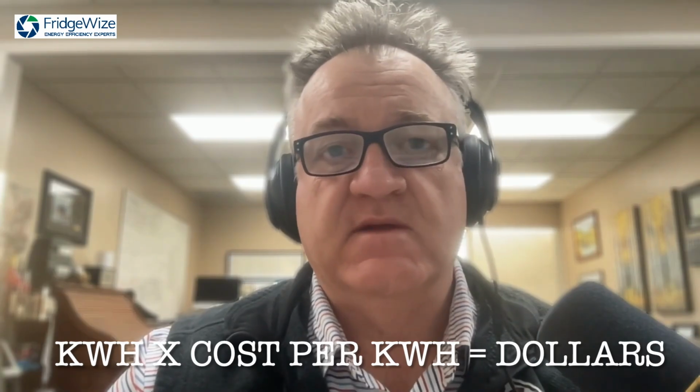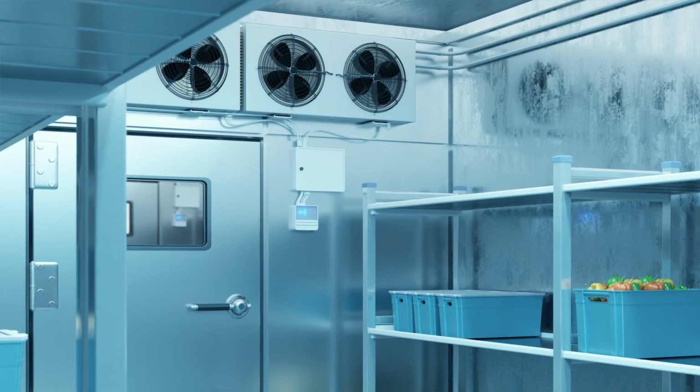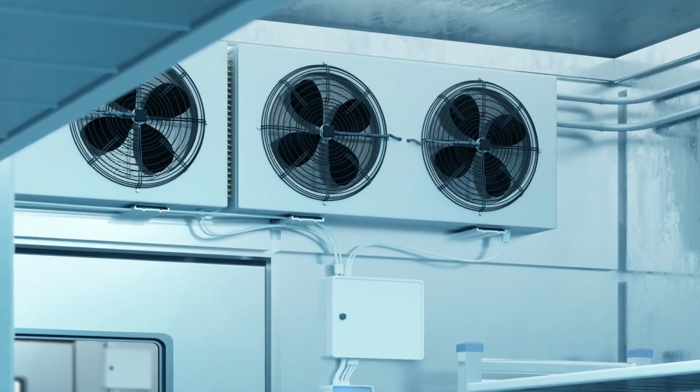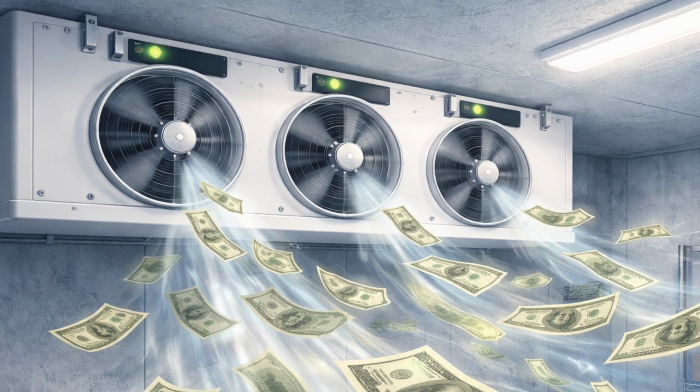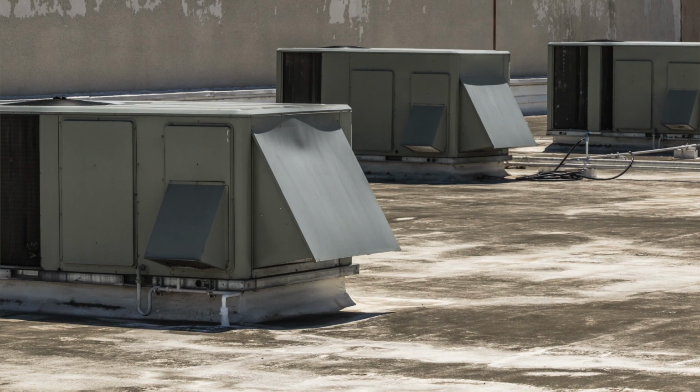And with simple motors like refrigeration motors with constant runtimes, it's very easy to take the amps and the volts and runtime and get the usage of a motor before you retrofit it, as well as the usage of the motor after you retrofit it. Dropping in a new EC motor into a walk-in evaporator will reduce the amps by up to 70%. Simple calculation will get you to kilowatt hours, and you can show the client exactly how much savings he's getting in that scenario. On the rooftop unit side, it's a little more complex.